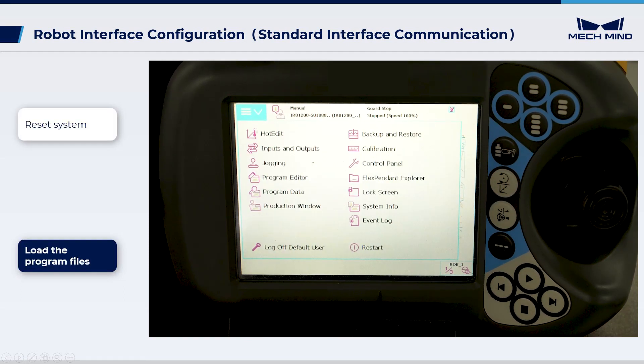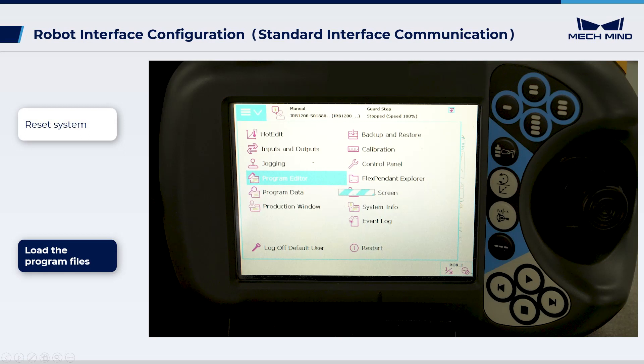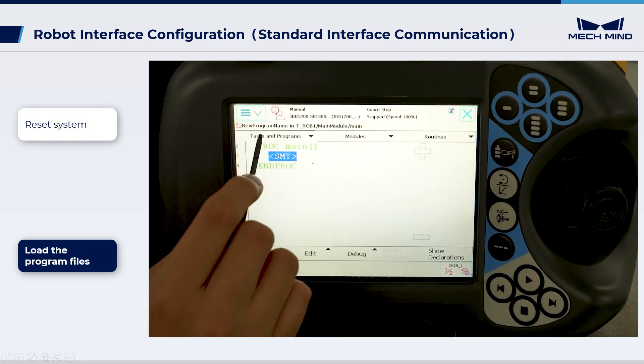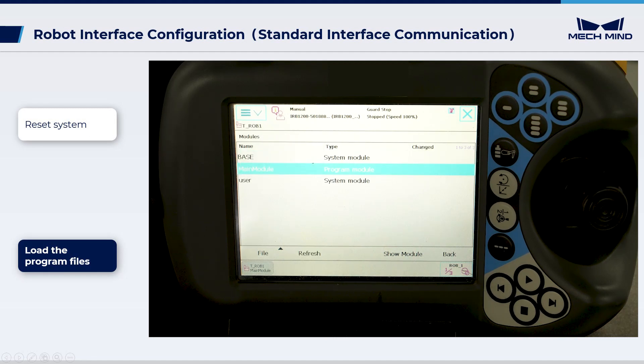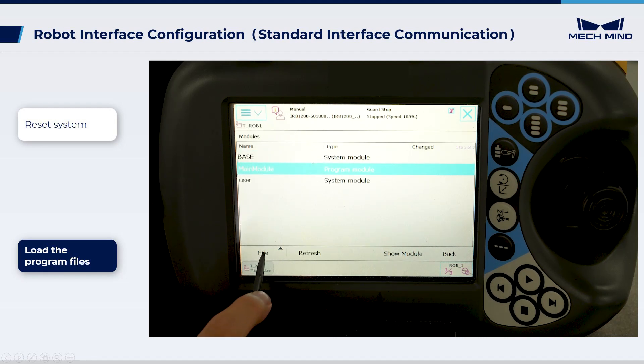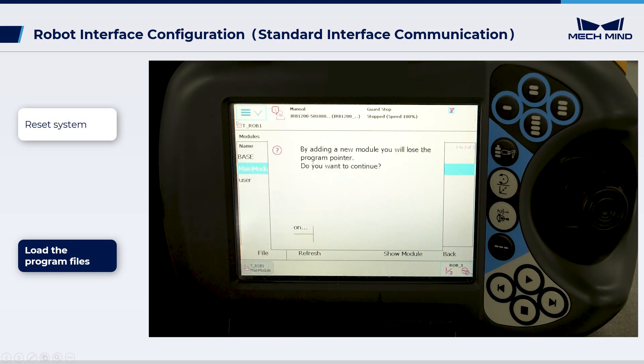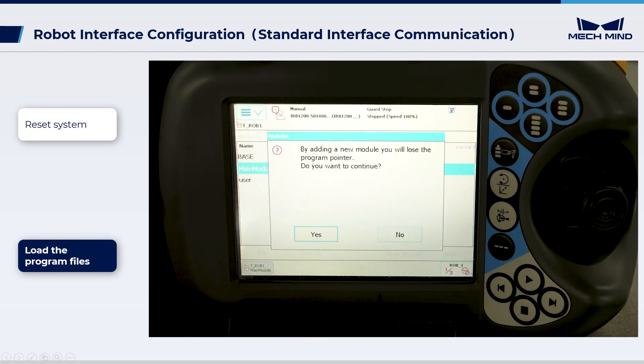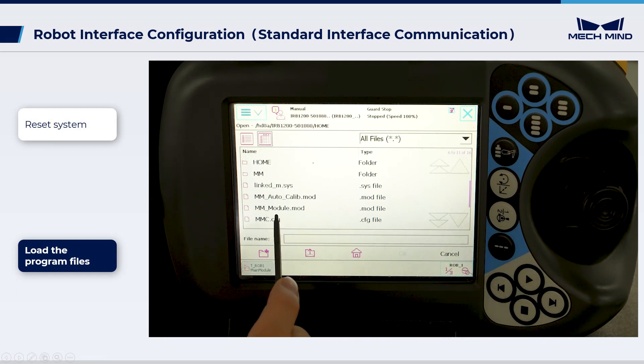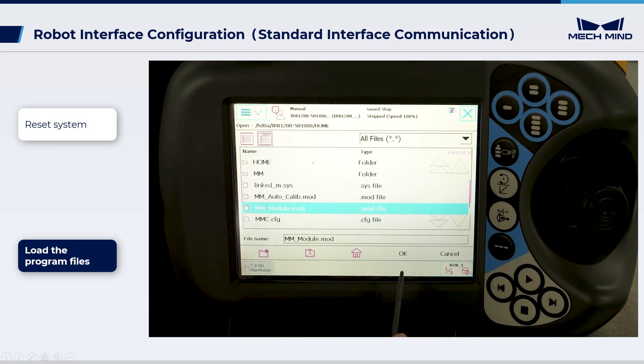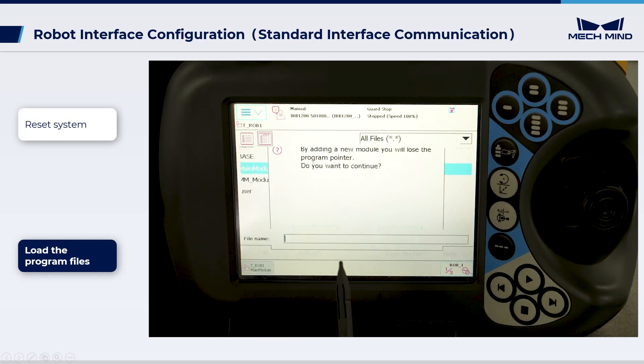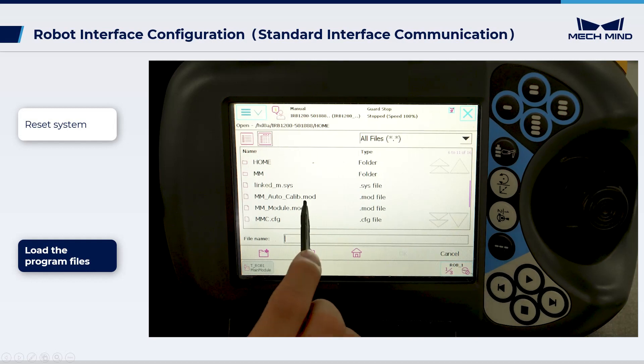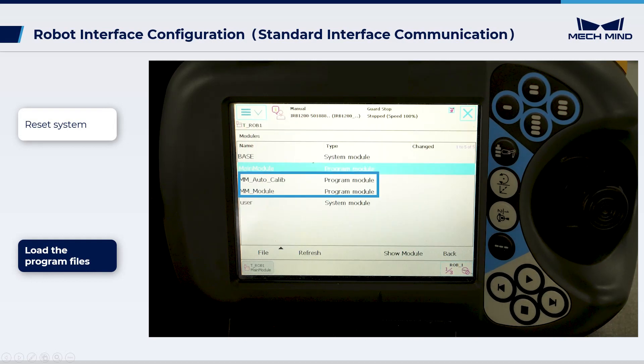To load program files, select Program Editor on the teach pendant. Choose Tasks and Programs. Select TROB1 and click Show Modules. Click File and choose Load Module. Select MMModule.mod on the USB flash drive and press OK to load the module. Follow the same instructions to load MMautocalib.mod. Verify that both files have been successfully loaded under TROB1.